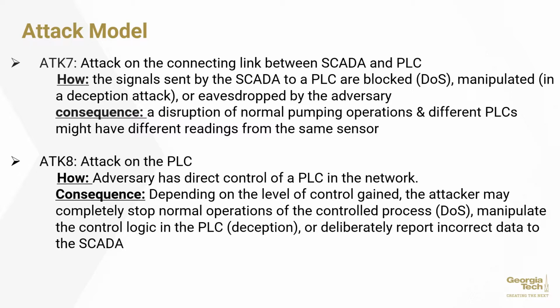Attacks 7 and 8 are also a different category, depending on what element has been attacked. Attack number 7 is an attack on the connecting link between SCADA and PLC, and it usually happens by the signals sent by the SCADA to a PLC being blocked and either manipulated or eavesdropped by the adversary, and consequently there is disruption of normal pumping operation, and different PLCs might have different readings from the same sensors.